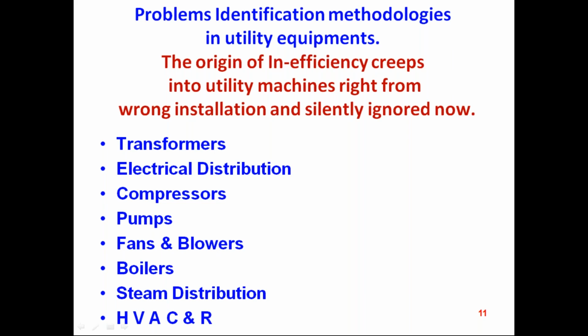Then come the compressors. Many of the industries have switched over from reciprocating compressors to screw compressors. If a screw compressor is operated between 60 to 80%, or only around 50% depending on the process load, a VFD has to be retrofitted in the screw compressor to get more energy savings for the given output. If it is loaded more than 80%, or fully near 90%, the VFD may not be needed for a screw compressor.